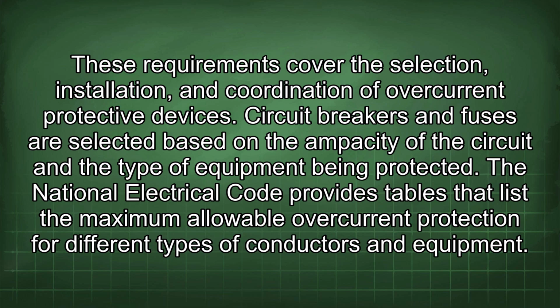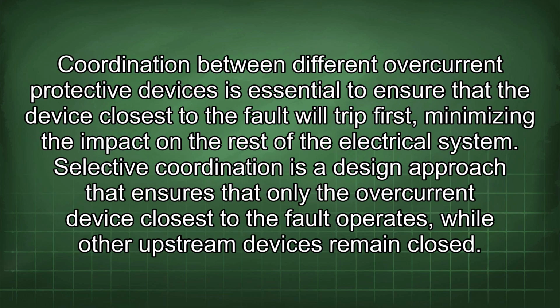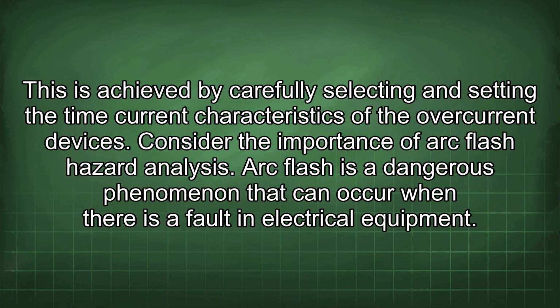Circuit breakers and fuses are selected based on the ampacity of the circuit and the type of equipment being protected. The National Electrical Code provides tables that list the maximum allowable overcurrent protection for different types of conductors and equipment. Coordination between different overcurrent protective devices is essential to ensure that the device closest to the fault will trip first, minimizing the impact on the rest of the electrical system. Selective coordination is a design approach that ensures that only the overcurrent device closest to the fault operates, while other upstream devices remain closed. This is achieved by carefully selecting and setting the time current characteristics of the overcurrent devices.